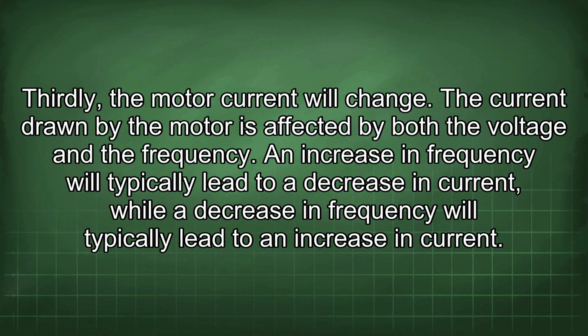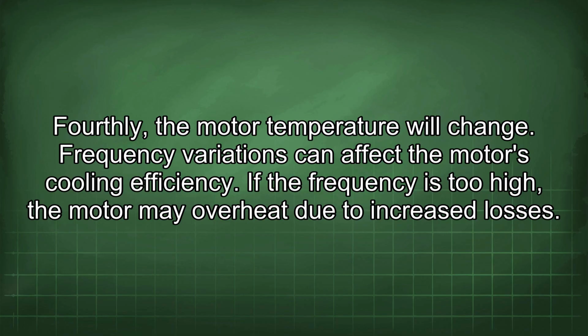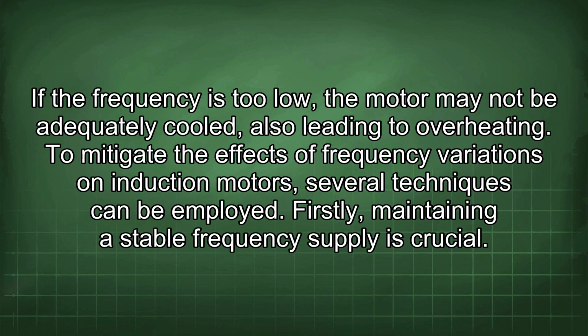Thirdly, the motor current will change. The current drawn by the motor is affected by both the voltage and the frequency. An increase in frequency will typically lead to a decrease in current, while a decrease in frequency will typically lead to an increase in current. Fourthly, the motor temperature will change. Frequency variations can affect the motor's cooling efficiency. If the frequency is too high, the motor may overheat due to increased losses. If the frequency is too low, the motor may not be adequately cooled, also leading to overheating.